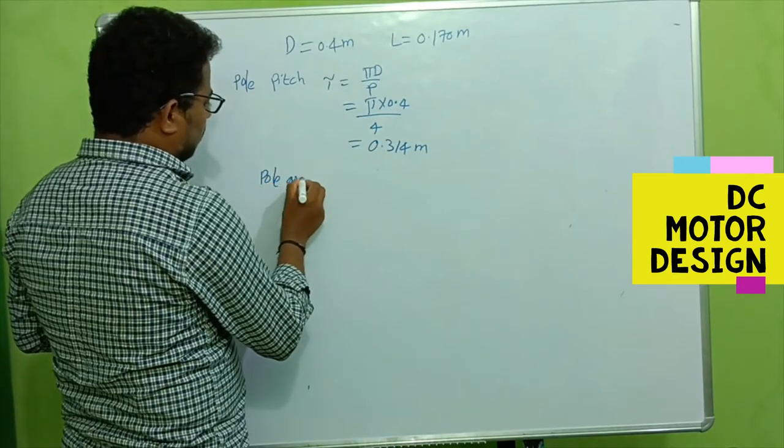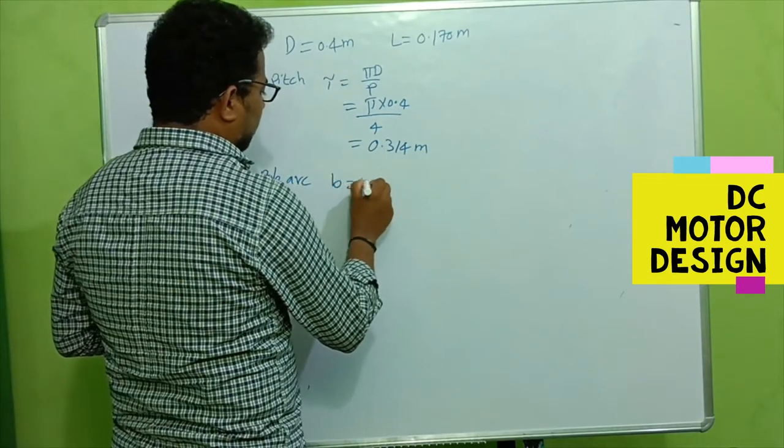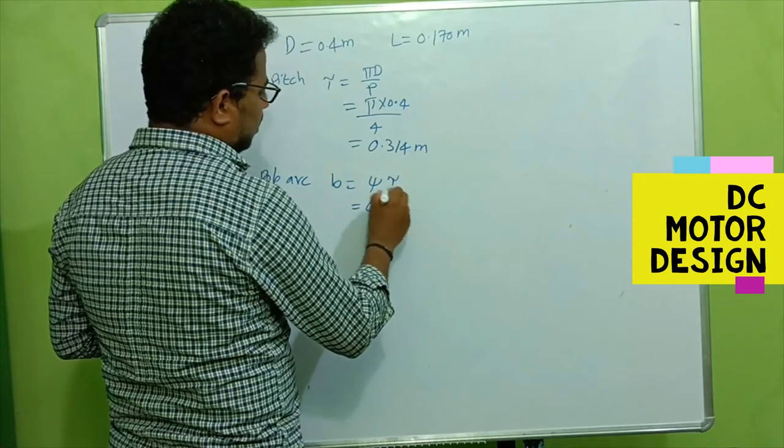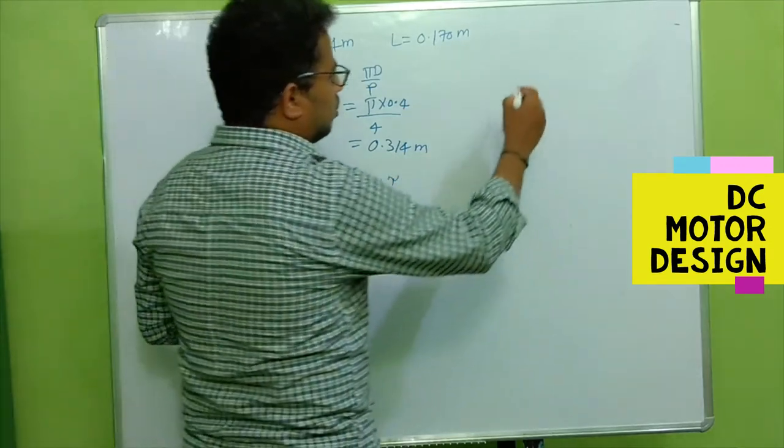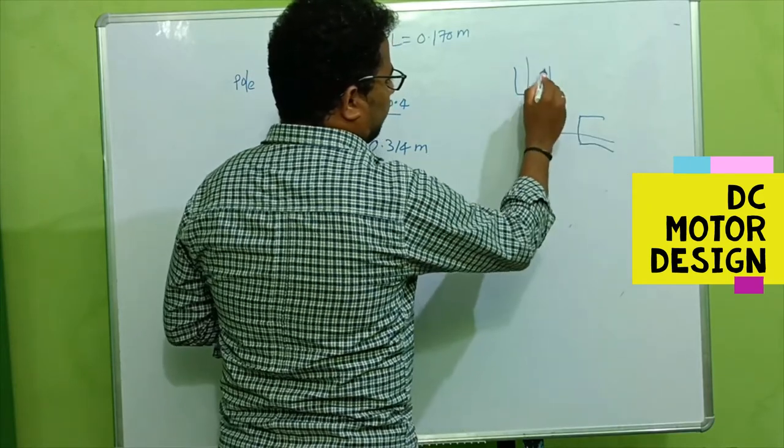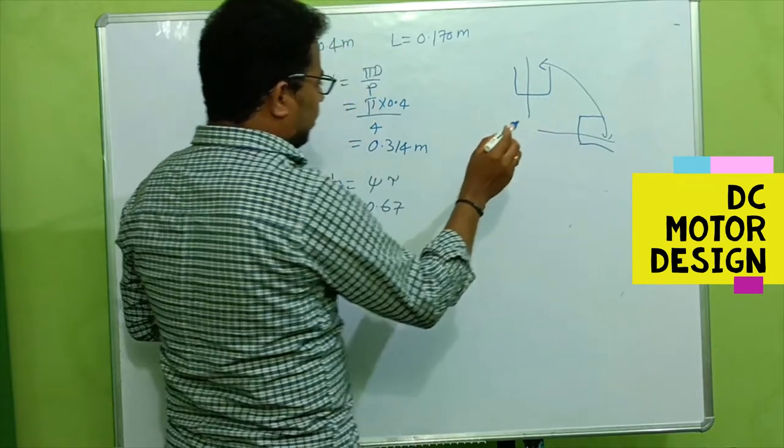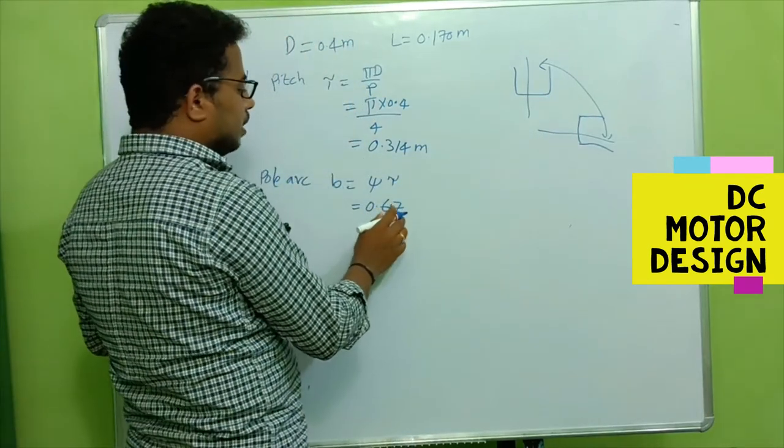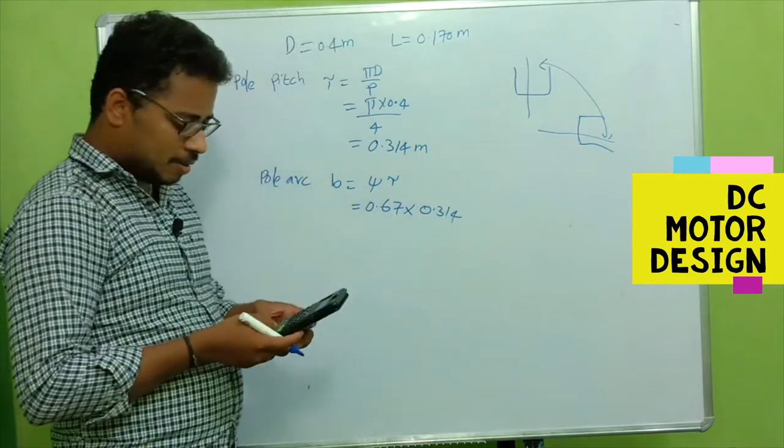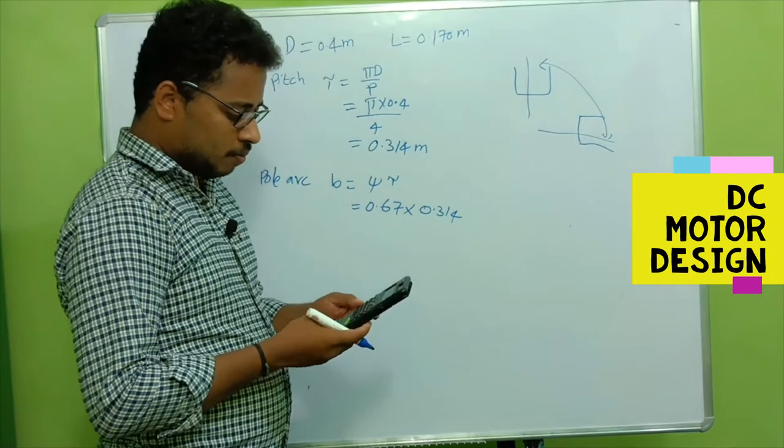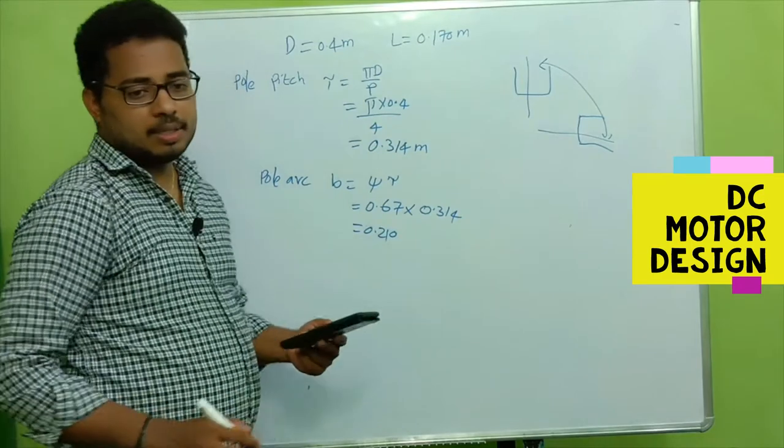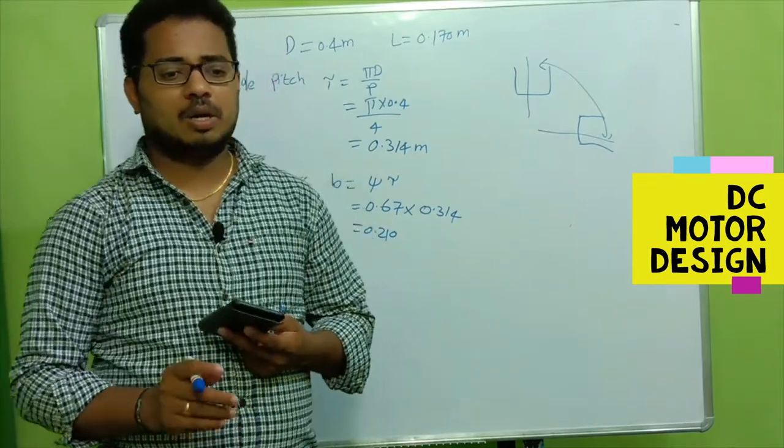Now, what is the pole arc? Pole arc, denoted as b, is ψ (psi) times τ. Psi is the ratio, generally we take 67 percent. So if this is one pole and this is another pole, then this is the pole arc. 67 percent is occupied by the pole arc. This is 0.67 times 0.314, which gives us 0.210. So 210 mm is the pole arc.